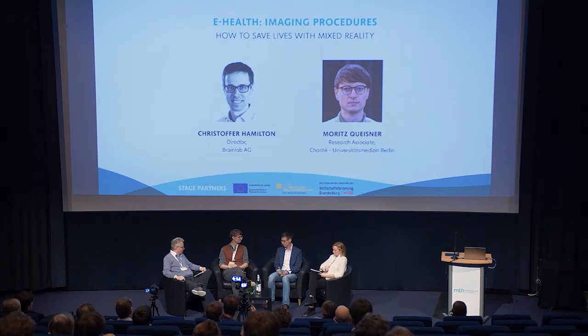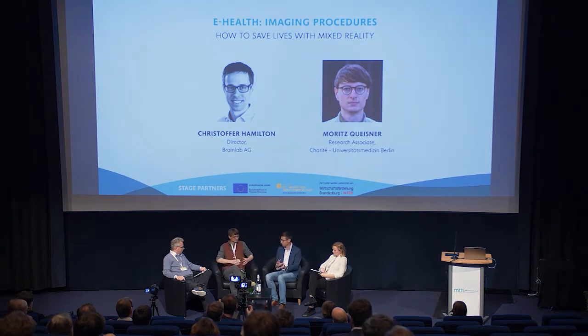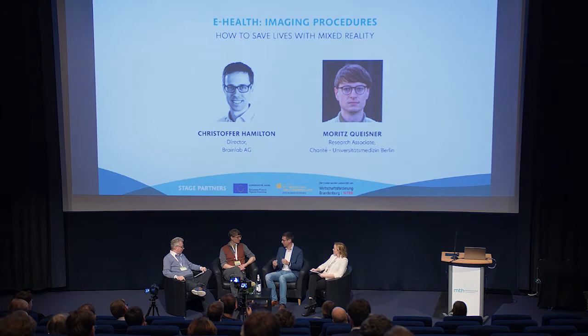So we follow basically the same procedures as the pharmaceutical companies. They're a bit different for medical devices, so they don't take quite as long, but we also require FDA approval. So I live in a more constrained world, I think, than Moritz, and we have to, of course, do clinical trials, do clinical investigations. So there are lots of time-consuming parts and things to do before you can release a product to the market.